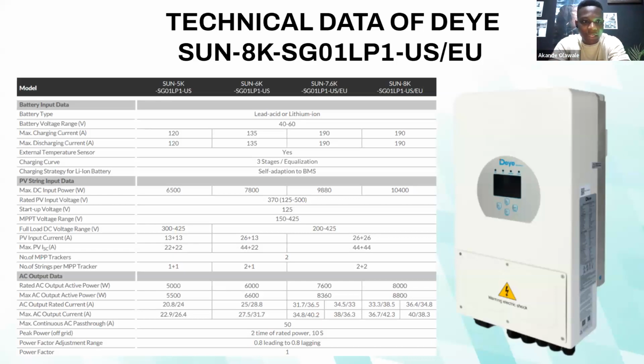The rated power input voltage is 370. MPPT voltage range, startup voltage is 125. The MPPT voltage range is 150 to 425. I think it gets up to 500, but to be on the safe side, you can do 425.